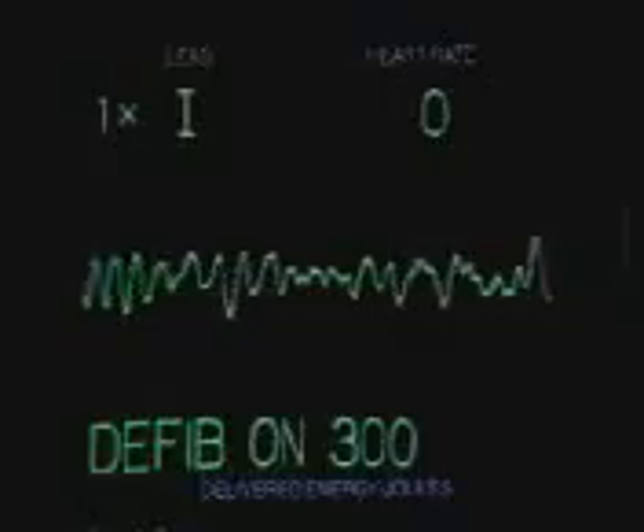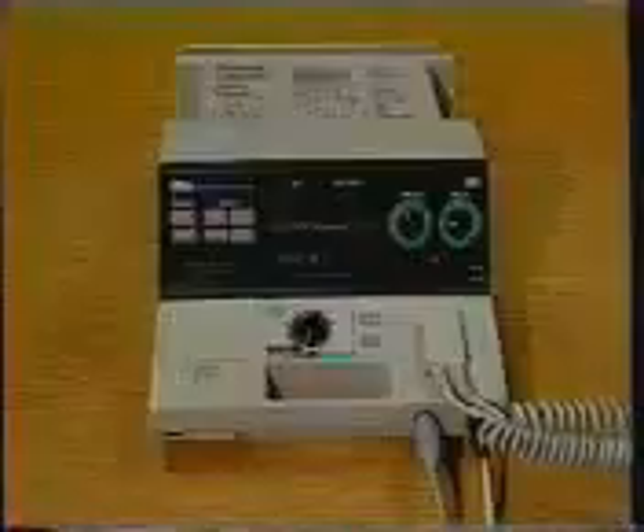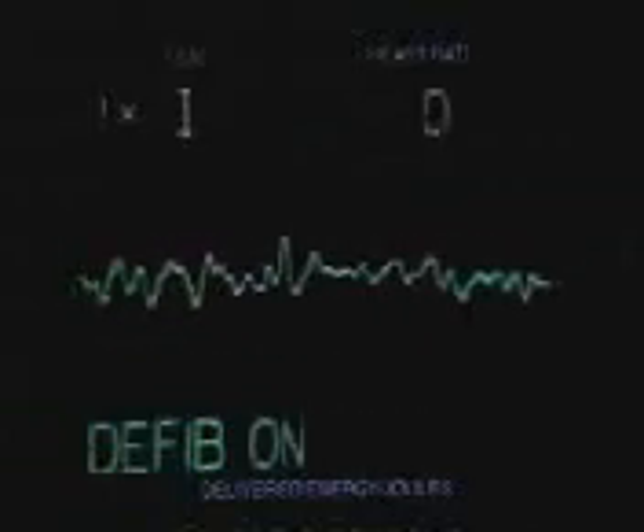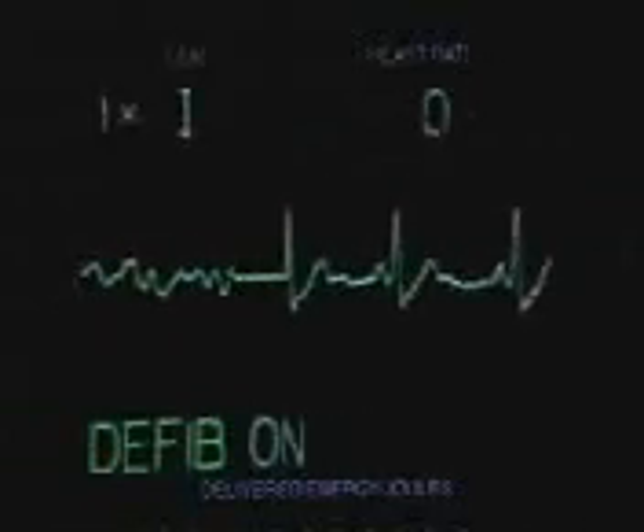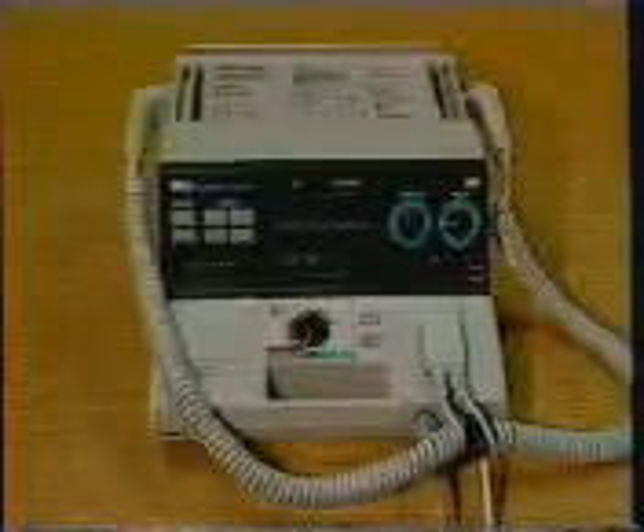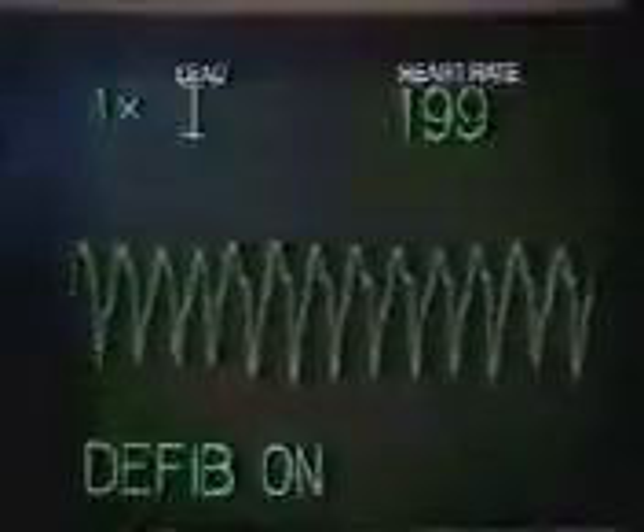Should you need to disarm the defibrillator after it has been charged, turn the selector switch to Monitor On or any other position. This will discharge the defibrillator internally. If a new energy is selected after charging is complete, you must press Charge to rearm the defibrillator. If the defibrillator is not discharged within 60 seconds after being charged, it will automatically discharge the energy internally. 10 seconds prior to this auto discharge, the charge ready tone will beep intermittently. A paddle fault message will appear whenever the paddles are not seated in their connector properly.